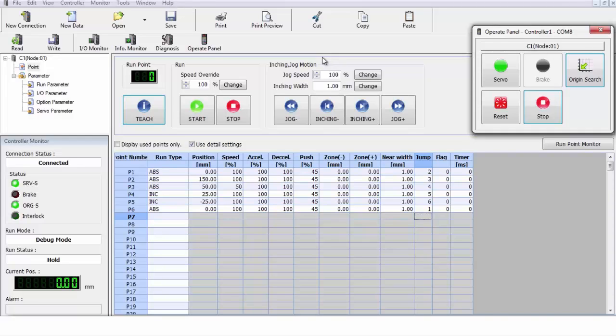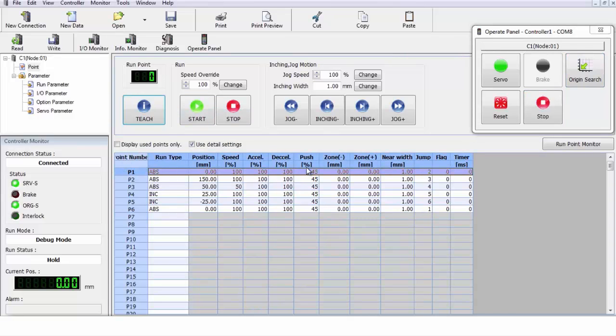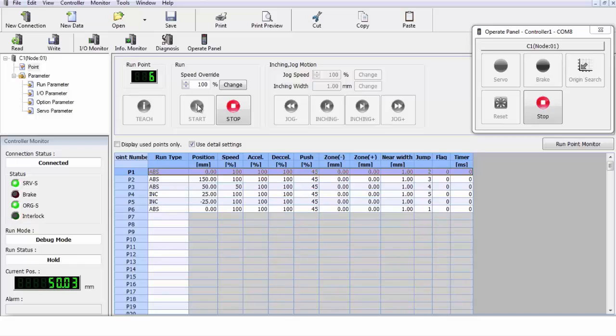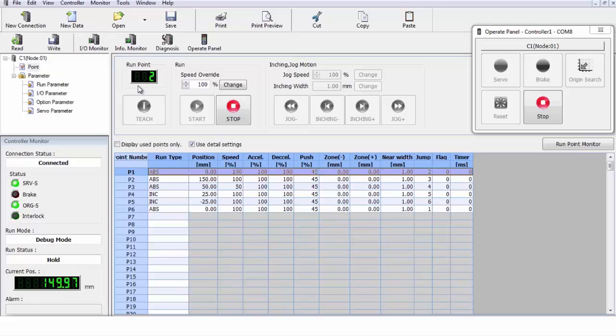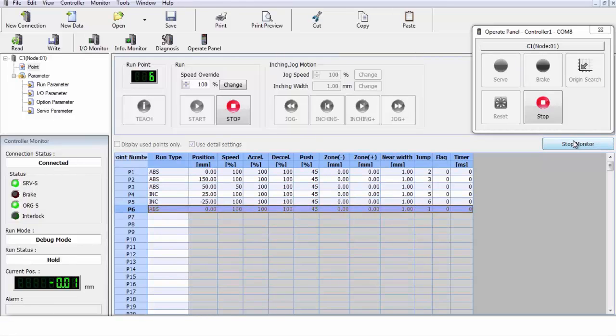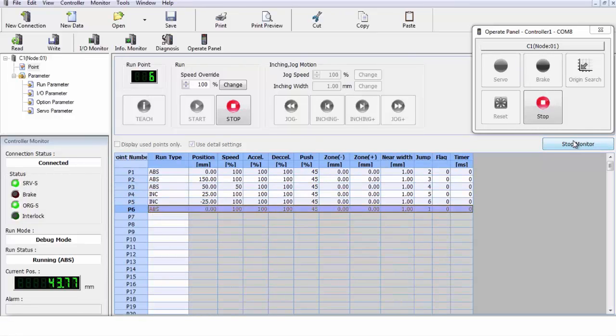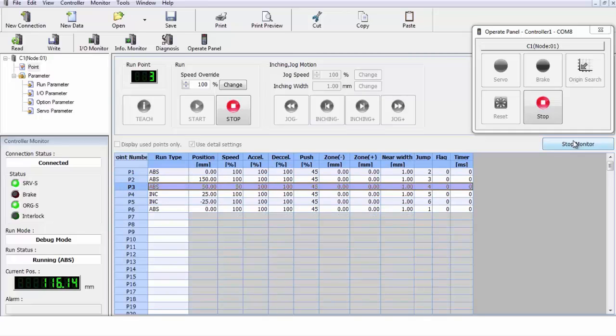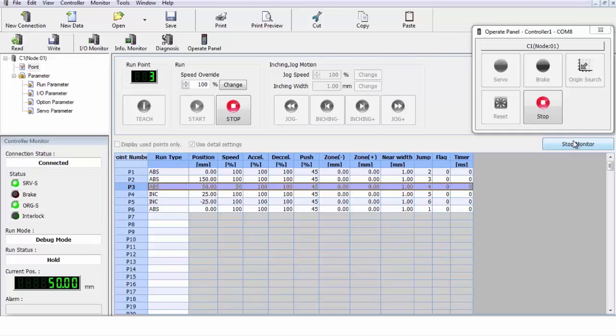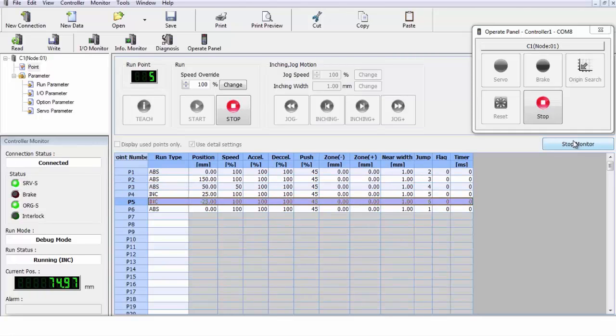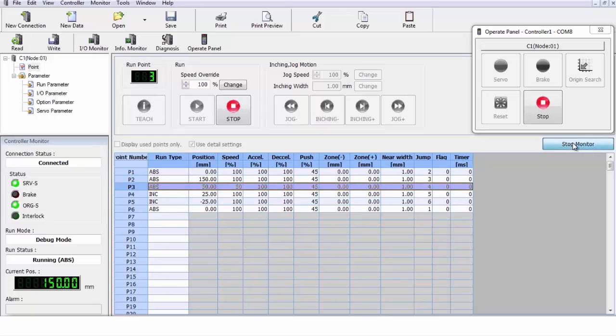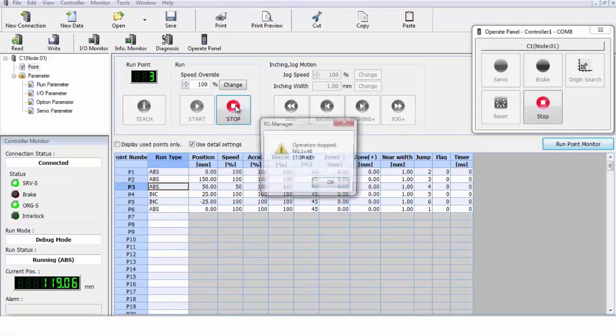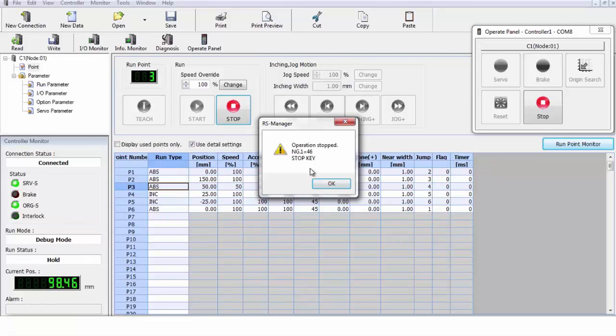Now we're ready to run our program. Before we can run the program, we have to select the position we want it to start at. So I'm going to start at position number one. I go up from there and I click on start. And our robot starts executing the program. Now if you see in the run point indicator up here, it tells us which position is actually being executed at what time. And then we can go down here and I can turn on our point monitor and it'll actually show you on the program as it executes each of the points. Now down in the lower left hand corner, you'll see we have our position indicator. That position indicator is showing the current position of the robot and what point is actually being executed at the time. I'm going to turn off this run monitor and we'll go up here and we'll stop the robot from running. So we've stopped our operation.